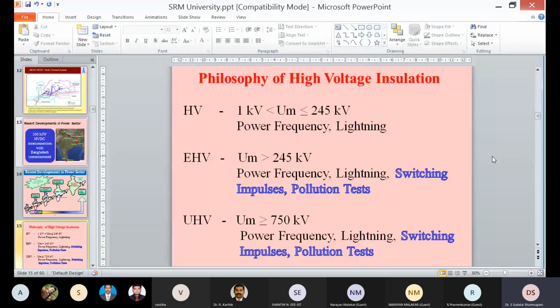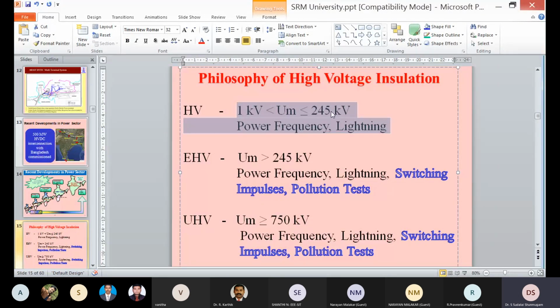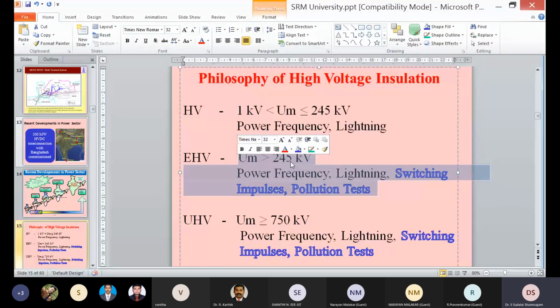According to IEC 60071, the high voltage line voltage level is between 1 kV and 245 kV. And the critical point here is that between 1 kV and 245 kV system voltage, we are testing only for power frequency and lightning impulse voltage. I repeat, when the system voltage is between 1 kV and 245 kV, we are concentrating only on power frequency voltage and lightning impulse voltage. However, when the system voltage is greater than 245 kV, switching impulse comes into the picture along with the pollution test. I repeat, when the system voltage is greater than 245 kV, that is extra high voltage, along with power frequency and lightning impulse voltage, two more things come into the picture. One is switching impulse voltage, another is the pollution test.